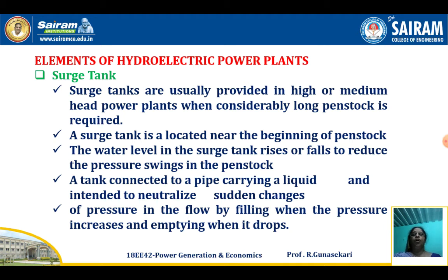When a considerably long penstock is required, a surge tank is located near the beginning of the penstock. The water level in the surge tank rises or falls to reduce the pressure swings in the penstock. It is a tank connected to a pipe carrying a liquid and intended to neutralize sudden changes of pressure in the flow, by filling when the pressure increases and emptying when it drops. This is the function of the surge tank.